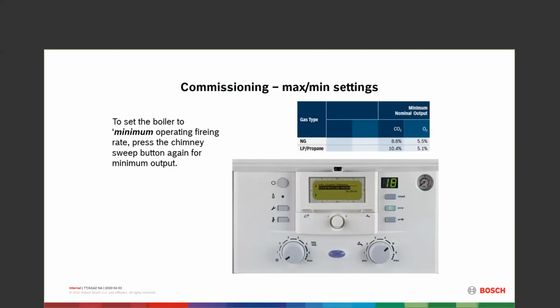All right, so on the control itself, to get into this control and how to get to minimum and maximum firing, you're actually going to push that little chimney sweep button. The little guy with the ladder, the serviceman, that guy right there. Push and hold that a couple of seconds, usually about 4 or 5 seconds. It's going to light up and the display is going to change a little bit. So once you press and hold that and get it lit up, that display should show you, for low fire, you're looking for 2 dashes. It's going to show you 4, then 6. Press it again. It's going to show you 2 dashes. 2 dashes, low fire.